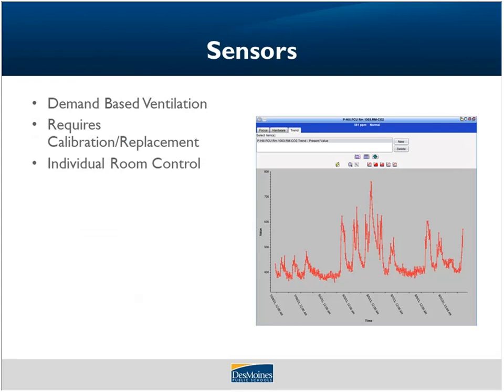We use sensors throughout the district to run our systems efficiently. Temperature and CO2 seem to be the most important, of course. Here's a trend graph of a classroom CO2 sensor at one of our elementary schools. It's a snippet out of our building automation system. This sensor controls the VAV box to change the damper position and provide the correct amount of fresh air. This trend goes back 8 days. From the information, we're able to tell when this room was occupied and can see that the highest CO2 concentrations in the classroom got to around 800 parts per million.